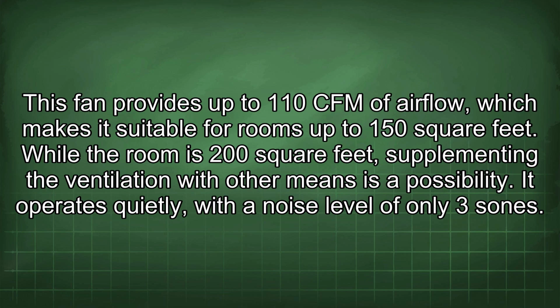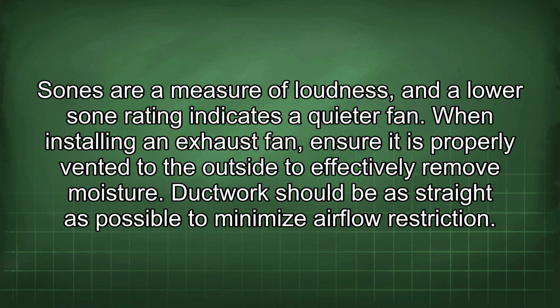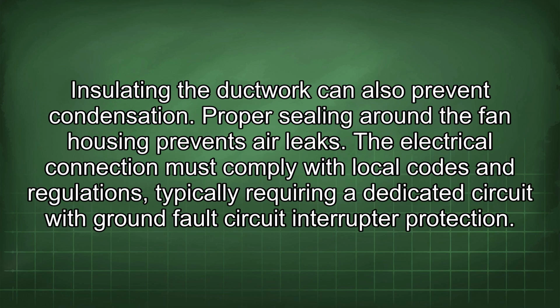It operates quietly with a noise level of only 3 sones. Sones are a measure of loudness, and a lower sone rating indicates a quieter fan. When installing an exhaust fan, ensure it is properly vented to the outside to effectively remove moisture. Ductwork should be as straight as possible to minimize airflow restriction. Insulating the ductwork can also prevent condensation. Proper sealing around the fan housing prevents air leaks.